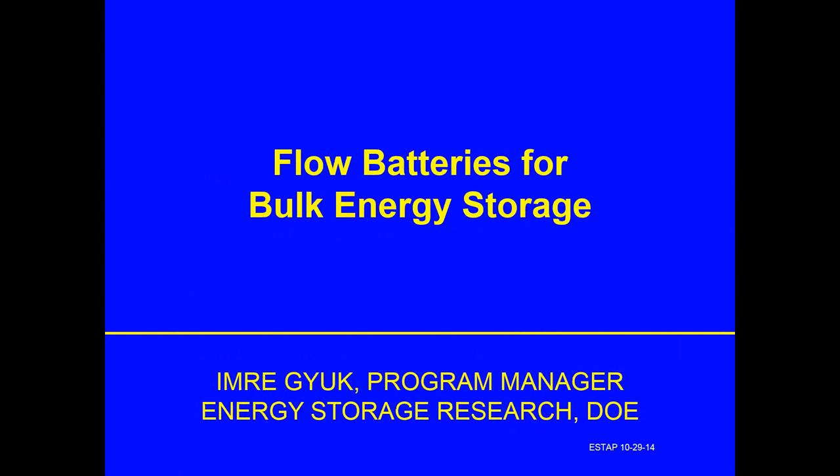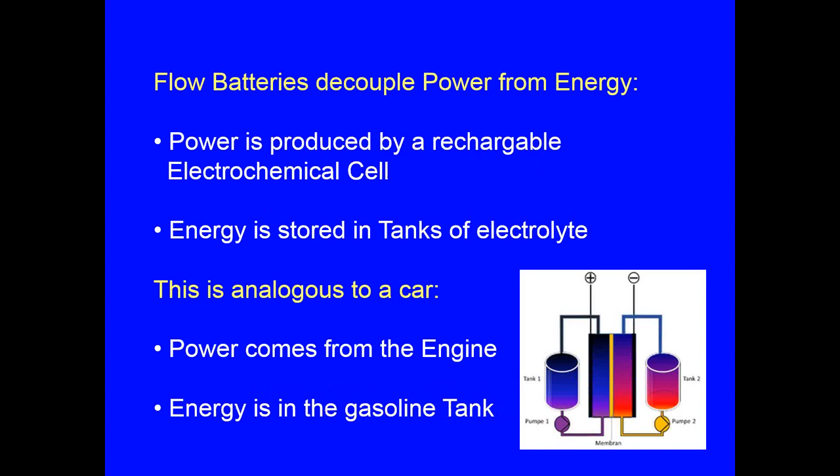Hello, I'm Imre Gyuk. I'm the program manager for energy storage research at the Department of Energy. We are very happy to have the ESTAP program provide these regular webinars to present information on energy storage to the states and to anyone who is interested. This is the second webinar on the topic of flow batteries. As a quick reprise: the characteristic feature of flow batteries is that they decouple power from energy. The power is produced by a rechargeable electrochemical cell in the middle, and energy is stored in tanks of electrolyte. If you want more energy, you just have more electrolyte and more tanks.